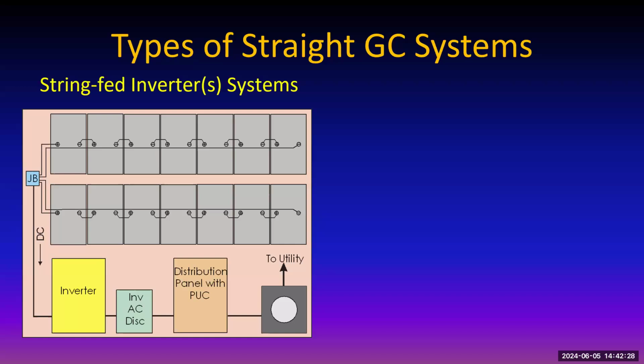So what it is going to do is hold up the whole string, and the total current it can produce is going to be limited by that one shaded module. So with a string fed inverter, you want to be really careful how you lay those modules out, because you don't want even one of those modules in one of those strings to be shaded, because that will in fact affect the performance of the entire system.